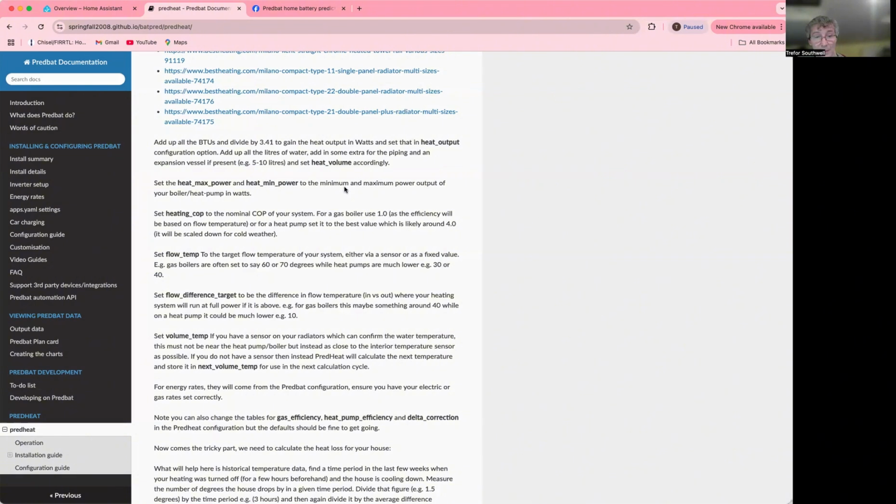Then there's the flow temperature. So whatever it's set to. So gas boiler, you might say it's 60 or 70. Some people might actually have a sensor for this, while the heat pump's normally 30 or 40. And set the flow difference target. That's the difference between the output temperature of the heating and the actual water itself.